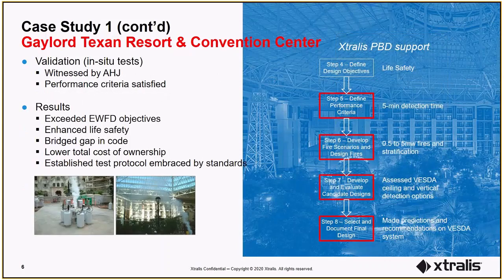With a smoke test apparatus centered to the center of the atrium, fire tests were conducted by local fire contractors and witnessed by fire consultants. The total heat generated from the radiant heaters was equivalent to a fast growth fire of 230 kilowatts.